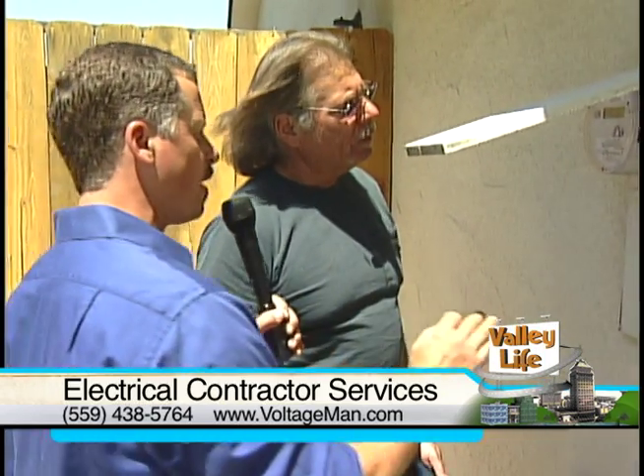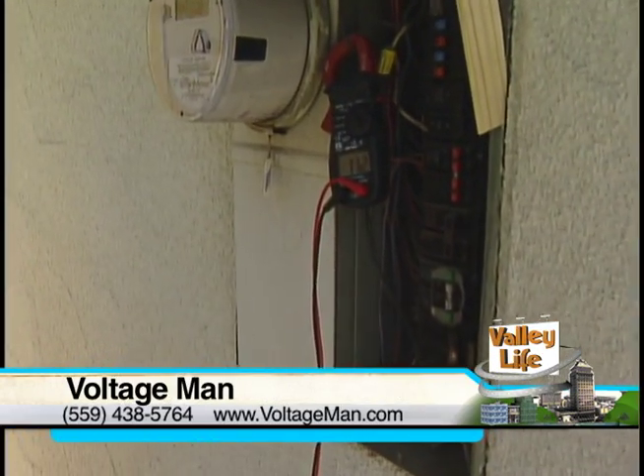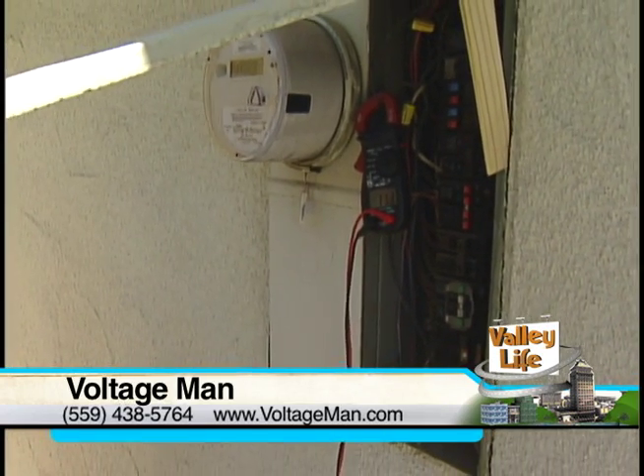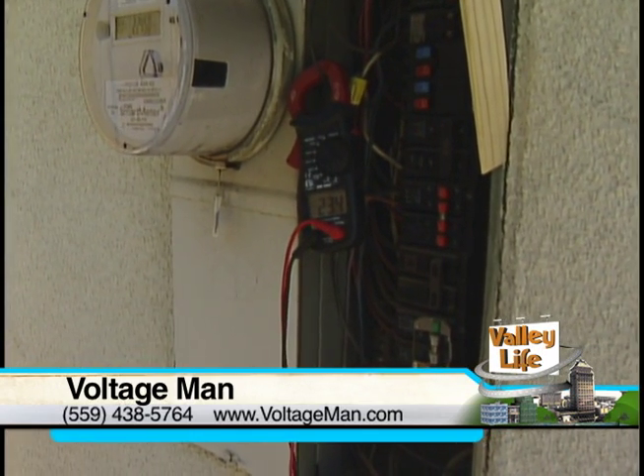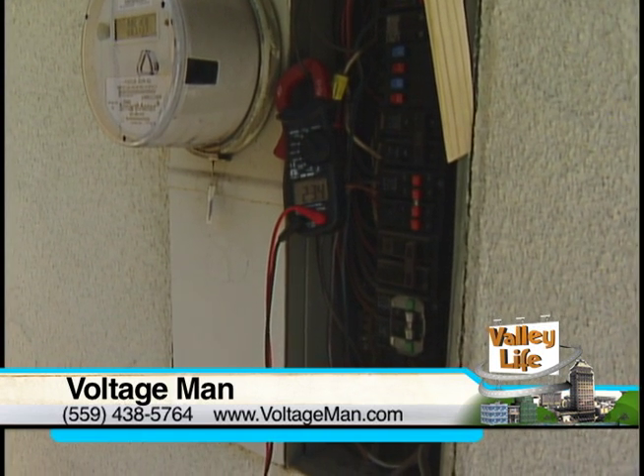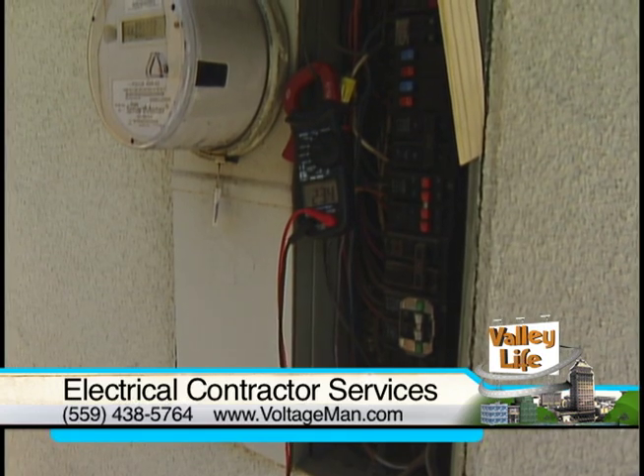Okay, so we've got one hairdryer going inside, so we can see we're at, what is that, 11? 11.2 amps, okay? And we have on a 15 amp breaker. Okay, Javier, let's turn on that other hairdryer. Okay, so now once you throw the second, look at that. We're at 23.4 amps, okay? Now 23.4 amps, these circuits are designed for 15 amps. What's going to happen is that wire is going to heat up, and eventually it's going to trip that breaker.